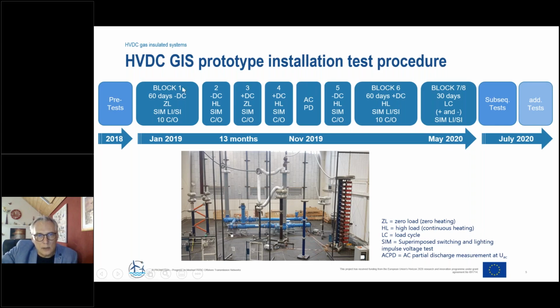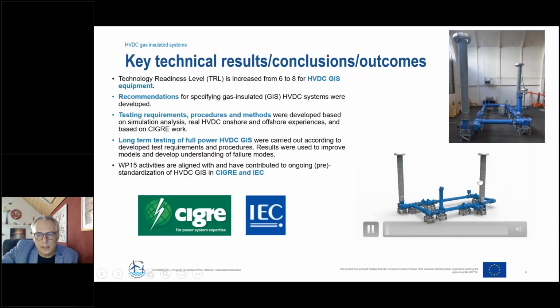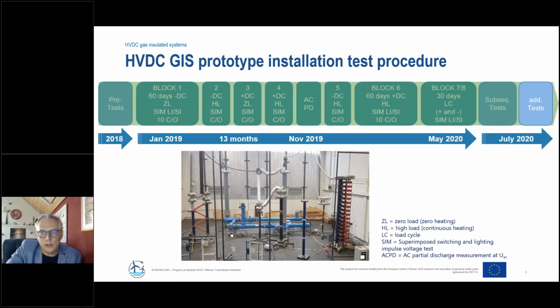The main test, as you can see here, consists of in total 6 blocks with a continuous DC voltage, and each block was roughly 60 days long and was completed with a superimposed lightning and switching impulse test and with operations of the switching elements, so the disconnectors, earthing switches, and fast acting earthing switch. The difference between the blocks was the DC voltage, so the polarity plus or minus, and also the load. That means some blocks were performed without current and other ones with high current, so 4,000 amps. The test started in the beginning of 2019 and was finished in July 2020, so some months ago.